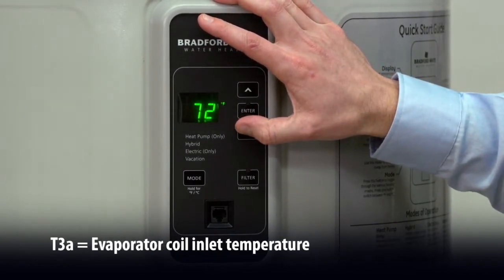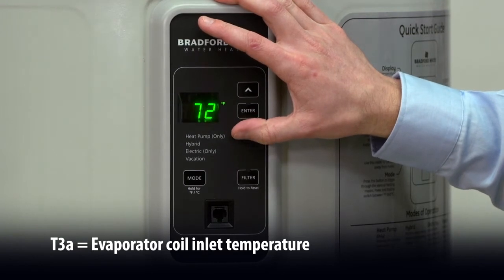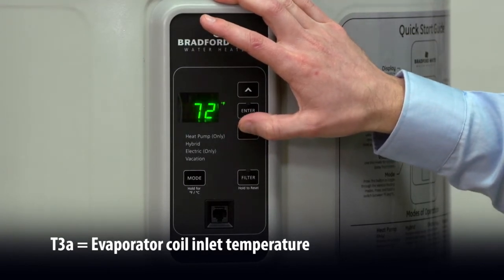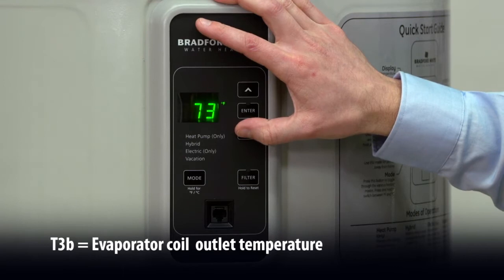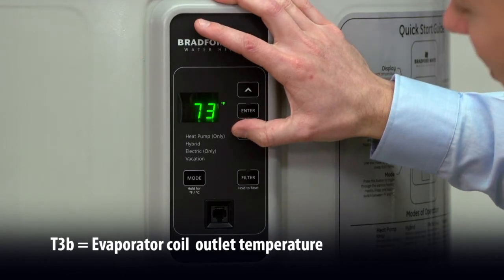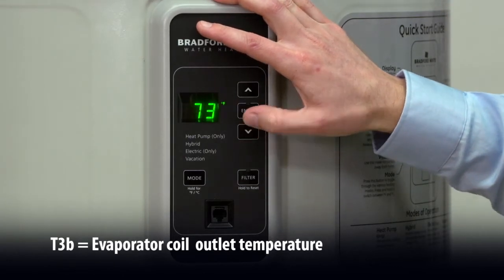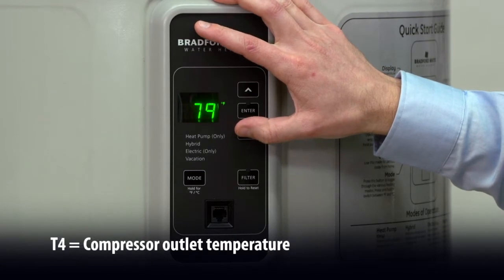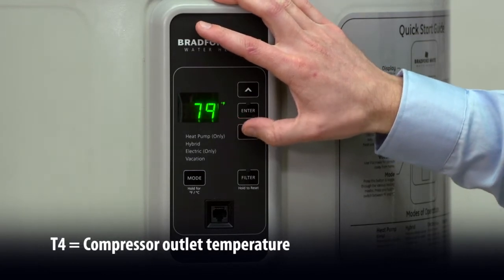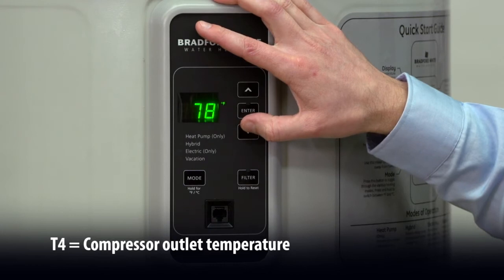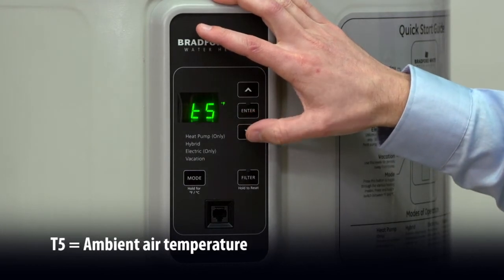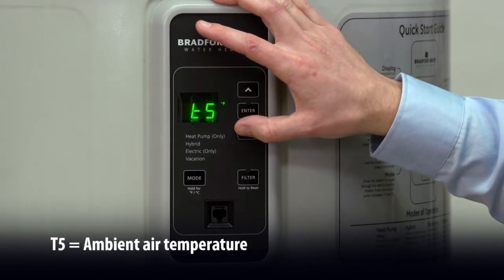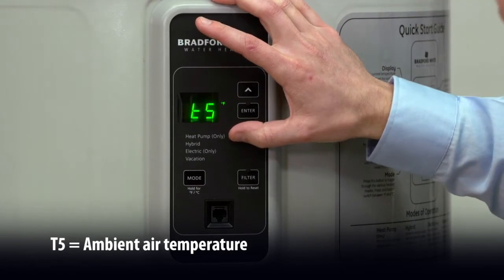Our T3A is our coil inlet temperature. That's going to be 72 degrees. Our T3B is our coil outlet temperature, also 73 degrees. The T4 sensor is our compressor outlet temperature, and that's right at 79 degrees. And finally, our T5 sensor is monitoring our ambient air temperature, and that puts us at 71 degrees.